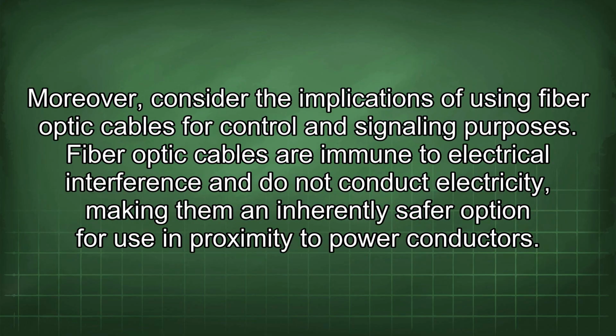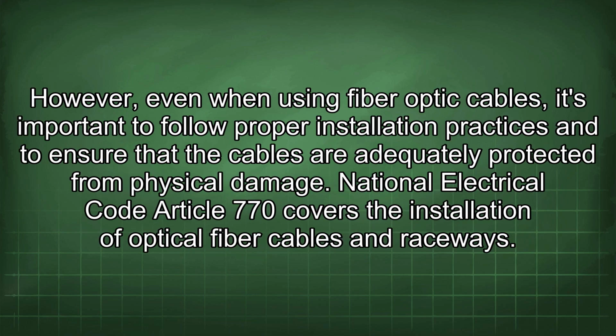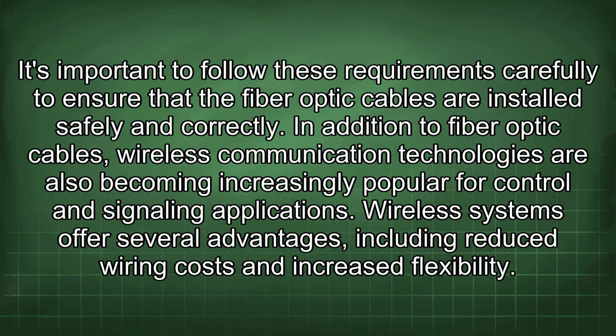Moreover, consider the implications of using fiber optic cables for control and signaling purposes. Fiber optic cables are immune to electrical interference and do not conduct electricity, making them an inherently safer option for use in proximity to power conductors. However, even when using fiber optic cables, it's important to follow proper installation practices and to ensure that the cables are adequately protected from physical damage. National Electrical Code Article 770 covers the installation of optical fiber cables and raceways. It's important to follow these requirements carefully to ensure that the fiber optic cables are installed safely and correctly.